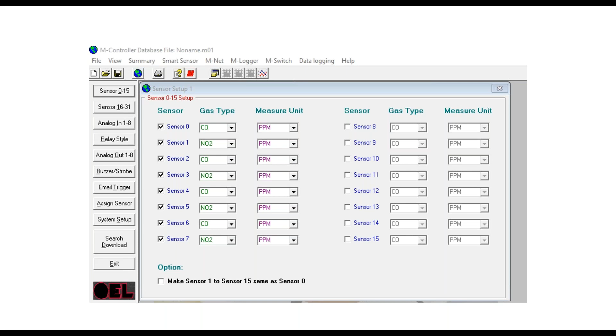The next step, we determine how many relays we're going to use. In this example, we're going to use 2 relays. So we're going to have 1 low alarm, 1 high alarm. And we're going to set that up as voting. So what that means is that if any one of the sensors reaches an alarm level, it's going to turn the relay on.